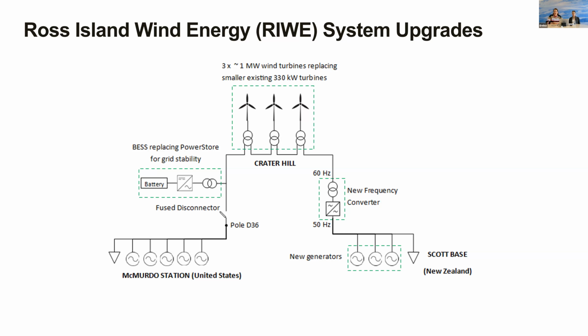Over on the Scott Base side, because Scott Base operates at the New Zealand frequency of 50 hertz, the whole of Scott Base operates like that. So we have a frequency converter located within Scott Base, just before the cable goes out and up the hill towards the wind farm, which converts the frequency to 60 hertz, matching the rest of the system. It's a very similar concept to the existing system, just all upgraded to represent a bigger wind capacity, meaning the cabling and everything needs to be upgraded as well.